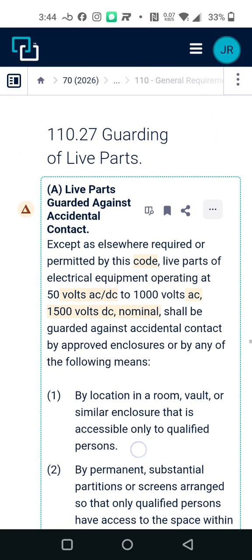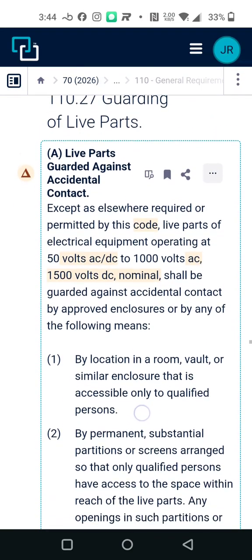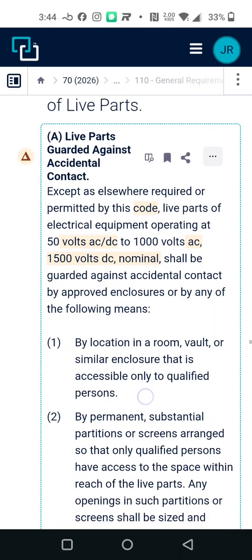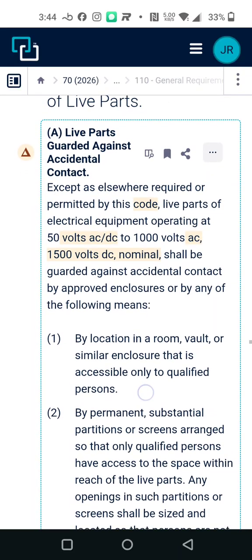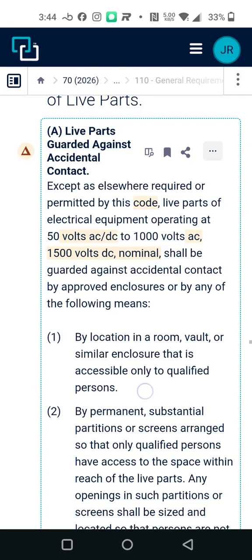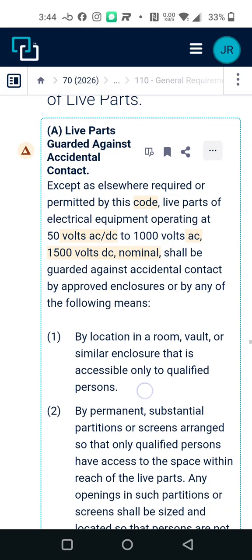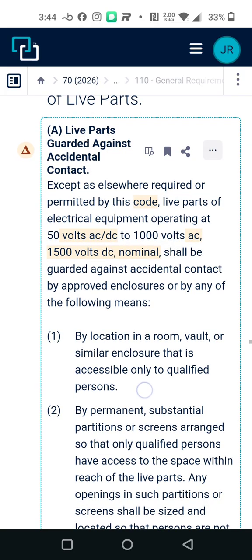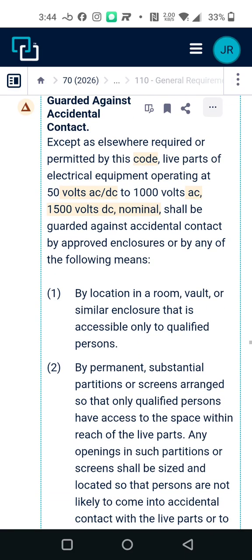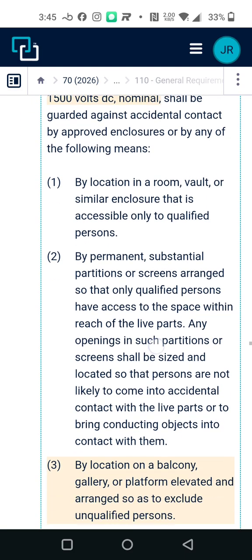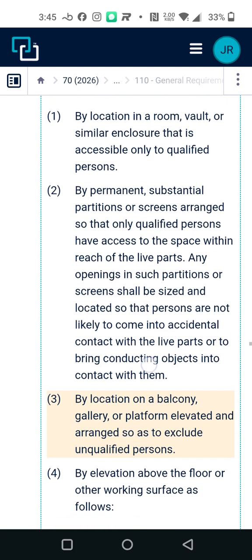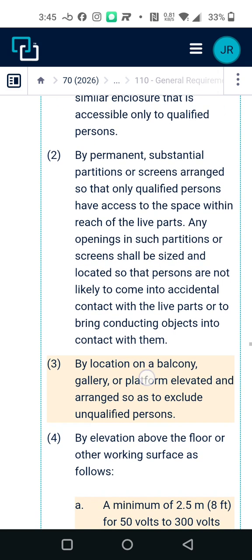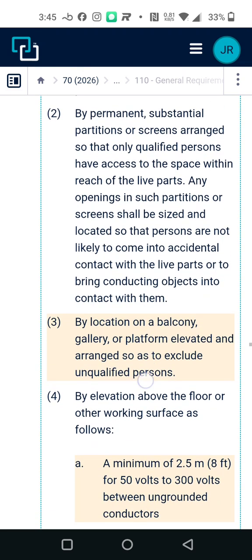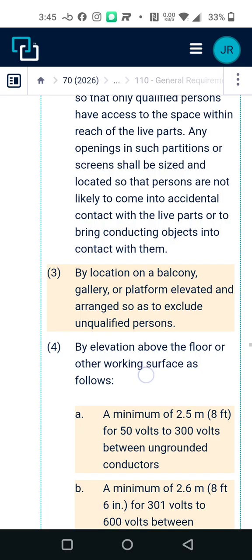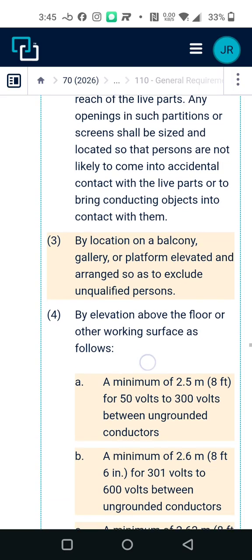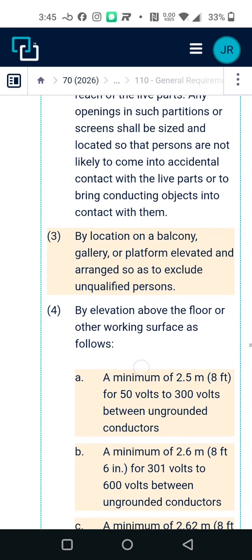Guarding of live parts. Live parts shall be guarded against accidental contact, except where elsewhere required or permitted by this Code. Live parts of electrical equipment operating at 50 volts AC to 1000 volts AC, 1500 volts DC nominal should be guarded against accidental contact by approved enclosures or by any of the following means: by location in a room, by permanent, substantial partitions or screens, by location on a balcony, gallery, or platform elevated and arranged so as to exclude unqualified persons.